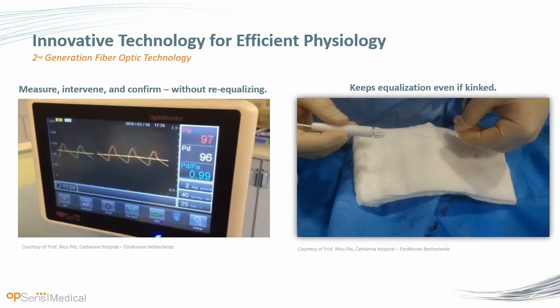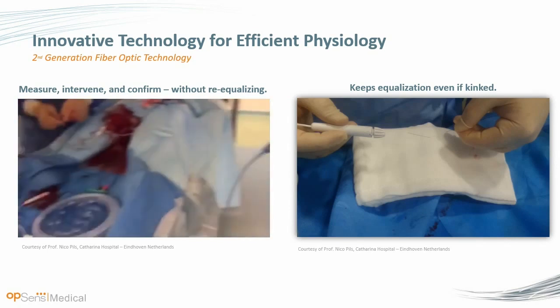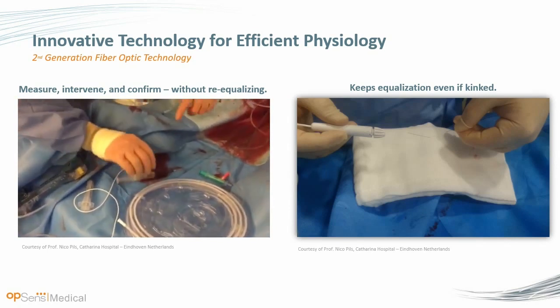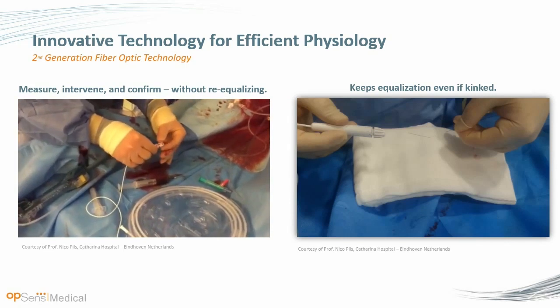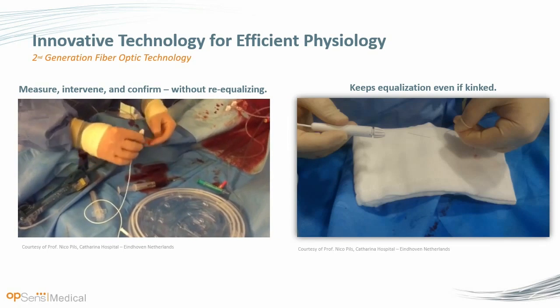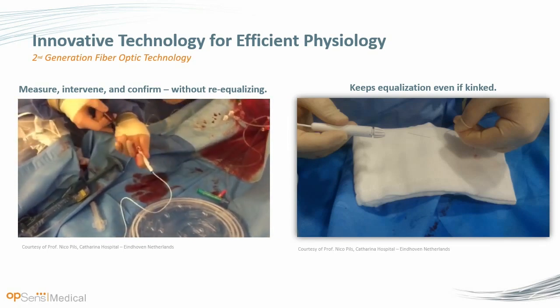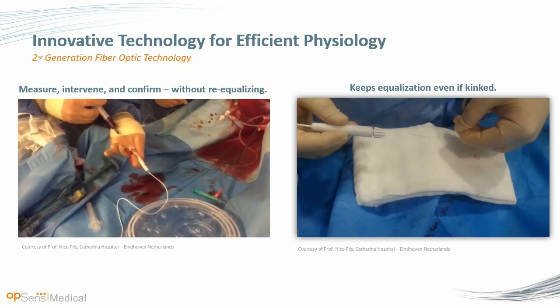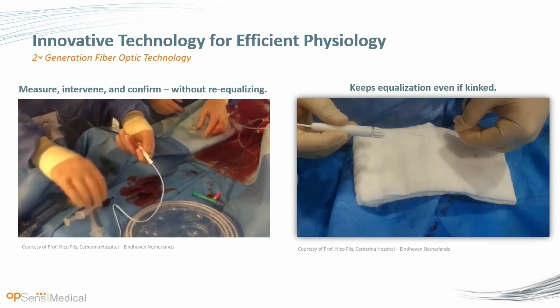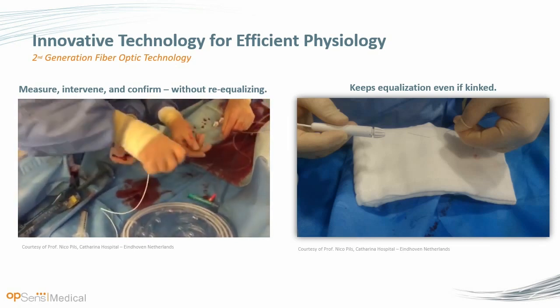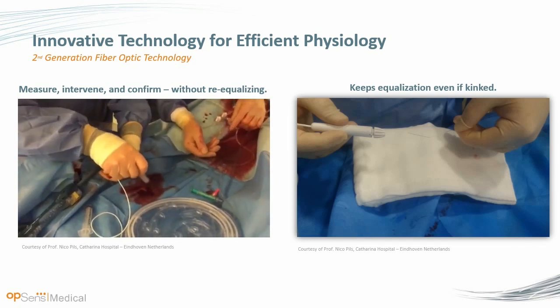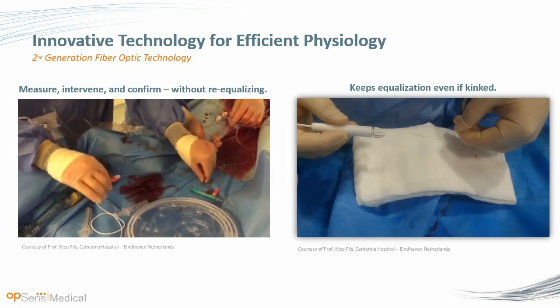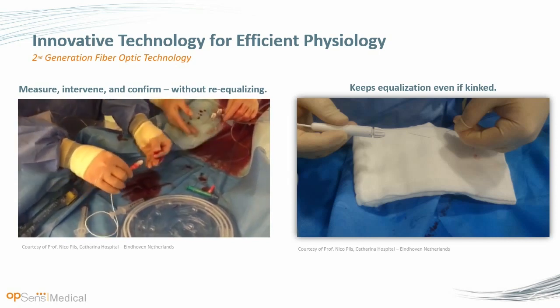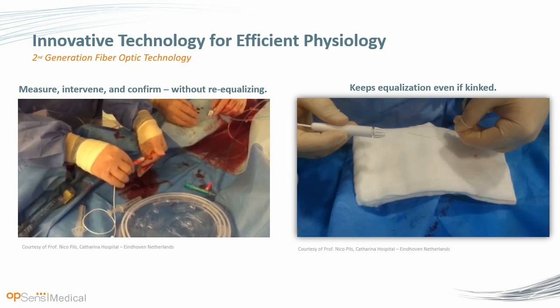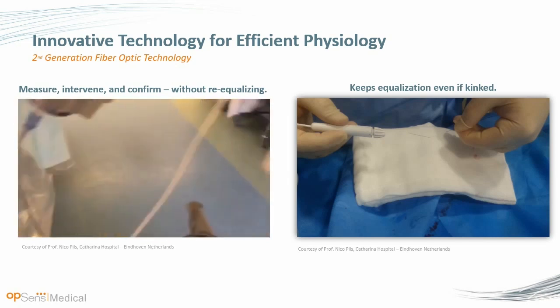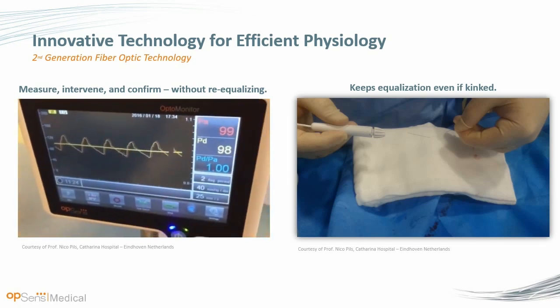And this is Nico Pils' video, and you can see here it's very robust to any blood clot, change in temperature. You can see here he did a little bit of experiment when he's disconnecting the wire, going to put some blood clot in the sensor housing, and you're going to see that the reading is still as good as it was. So the key here is you can connect, disconnect, and you don't have to re-zero. It's very, very stable. So when we do a PCI and you put some balloon, some stent, and you disconnect the wire, and then after 10, 15 minutes, you reconnect, you don't need to re-zero. So it's very, very accurate, and then you can move to the other vessel. You're going to see the measurement didn't change, even after blood and everything. So it's still 1.